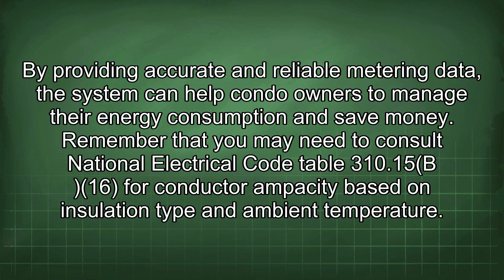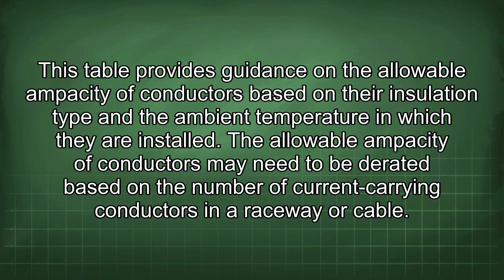Remember that you may need to consult National Electrical Code Table 310.15(B)(16) for conductor ampacity based on insulation type and ambient temperature. This table provides guidance on the allowable ampacity of conductors based on their insulation type and the ambient temperature in which they are installed. The allowable ampacity of conductors may need to be derated based on the number of current-carrying conductors in a raceway or cable.